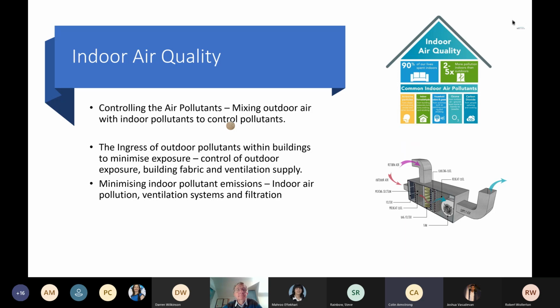So, control strategies. The control strategies to reduce the concentration of air pollutants in the indoor environment depend on the type and the location of the source and activity. Ventilation with outdoor fresh air will dilute and flush out pollutants derived from indoor sources, but it will not eliminate them completely. It's impossible at the moment. And in fact, the incoming air could also be polluted from an outdoor source that we're bringing in. It depends where the intake on a system is, or wherever your window is. There are so many factors to it. So care needs to be taken in selecting the correct mitigation strategy to give optimum indoor air quality for people's health and well-being.